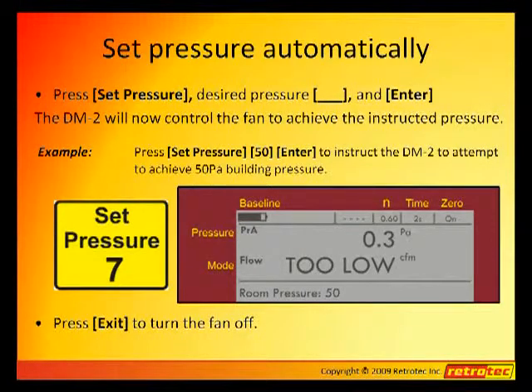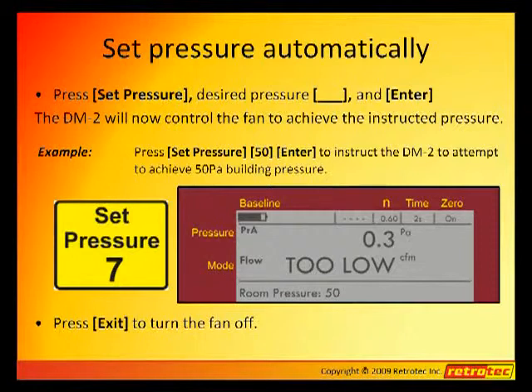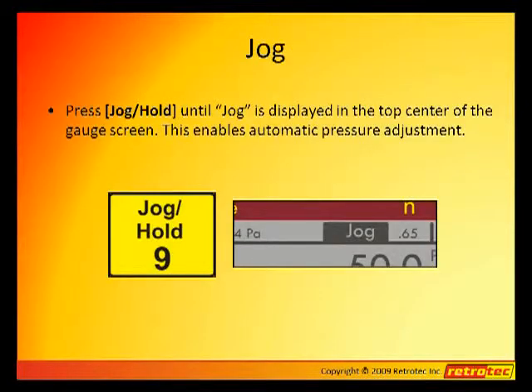For example, if we press the Set Pressure key, then 5, 0, Enter, we have just instructed the DM2 to attempt to achieve a 50 Pa pressure differential in the building. After an initial pressure has been set, the Jog function is now activated and can be utilized by pressing the Jog Hold key on the keypad until the word Jog appears on the top display bar.